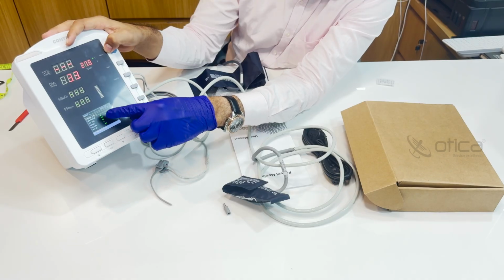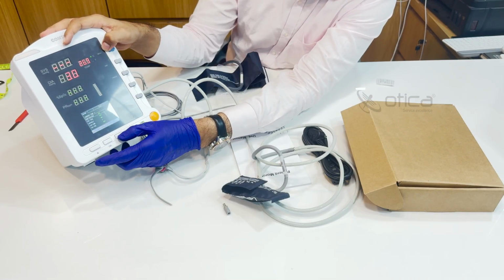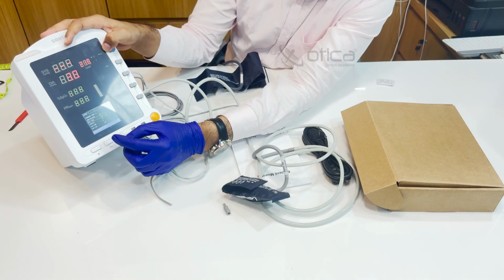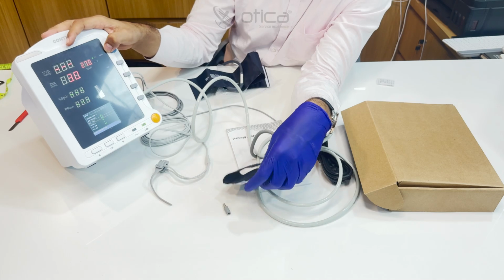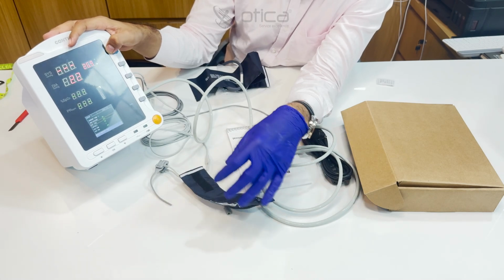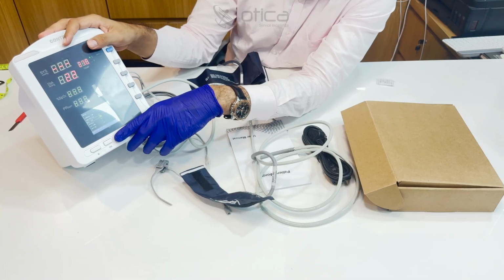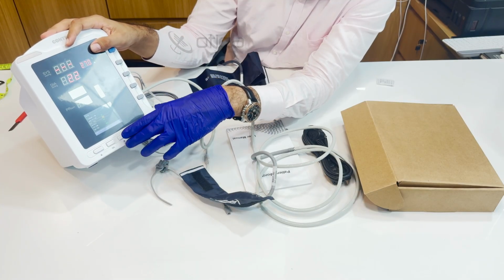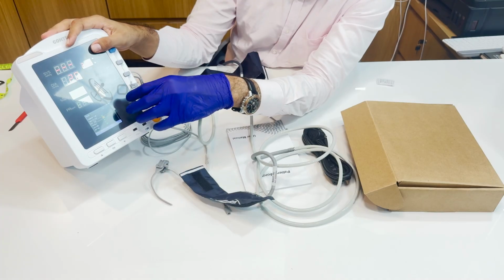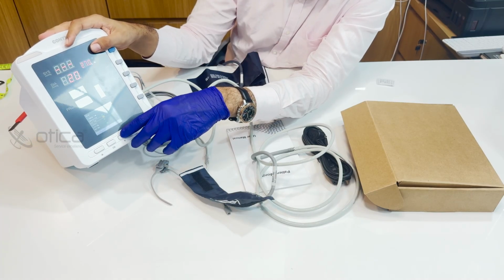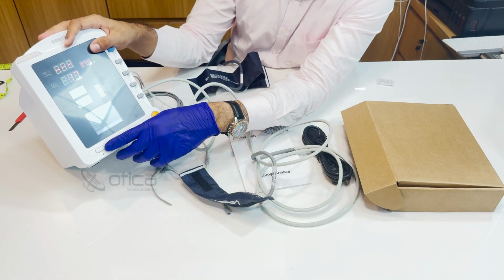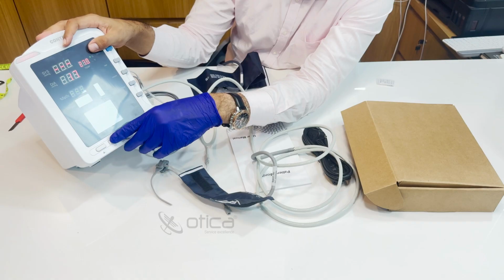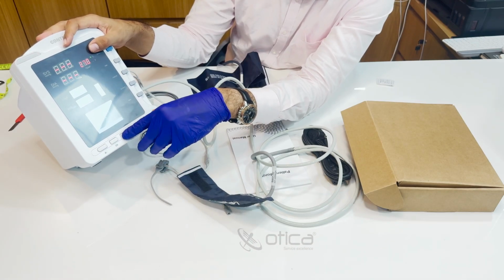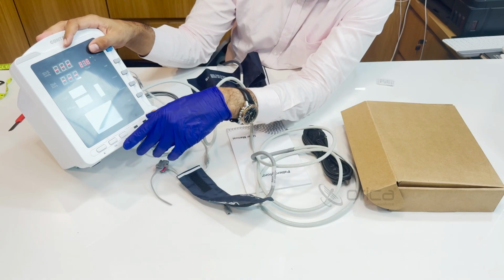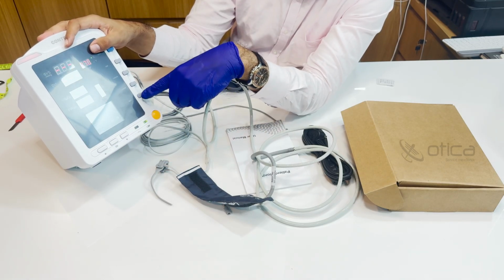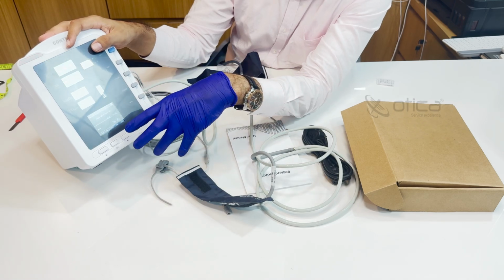If you do not select the patient type here as neonatal or pediatric, it will give you the adult pressure in blood pressure, so it will be harmful to the baby. So you have to make sure that the selected patient is the correct type. Like if you are applying this machine to an adult, you have to select adult, neonatal or pediatric. So we will put neonatal here, and then you have to come to exit, or you can also press the main button directly, so it will bring you to the main screen.